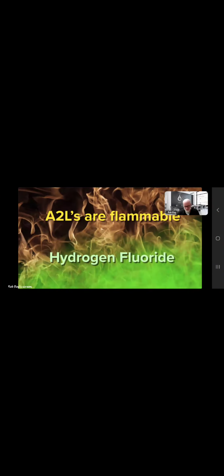Now, they figured this out when they were testing for automotive systems. Used to be 134A, an HFC, in all automotive. Now it's 1234YF, which is an HFO. When they were testing for these, it ignited. It releases hydrogen fluoride. A couple workers died. This is a very deadly toxin. So, not trying to scare anybody, but when this stuff ignites, we've got to do things the right way.